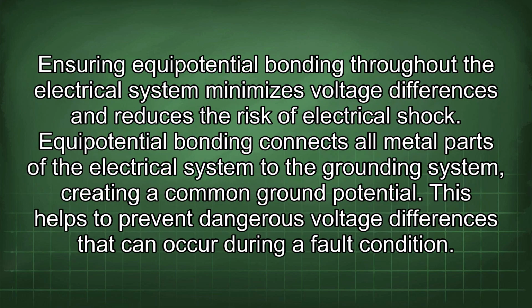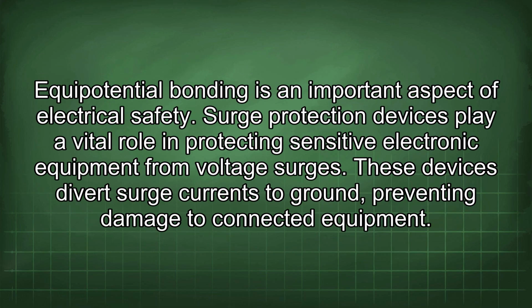Ensuring equipotential bonding throughout the electrical system minimizes voltage differences and reduces the risk of electrical shock. Equipotential bonding connects all metal parts of the electrical system to the grounding system, creating a common ground potential. This helps to prevent dangerous voltage differences that can occur during a fault condition. Equipotential bonding is an important aspect of electrical safety.